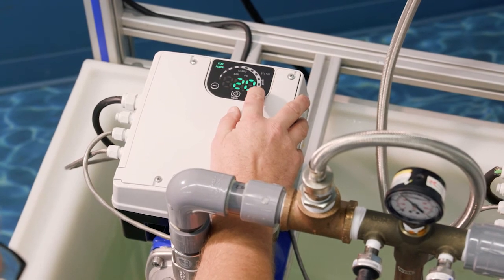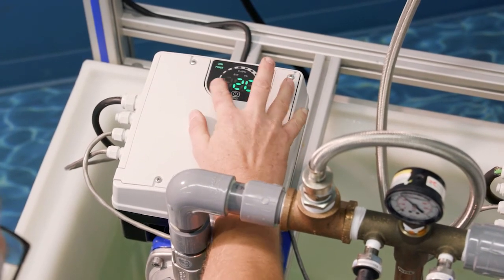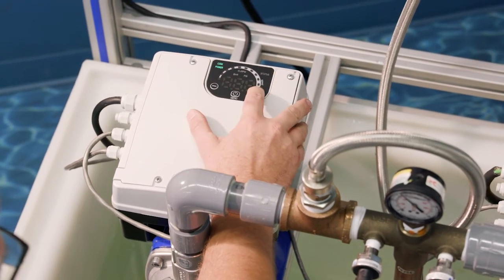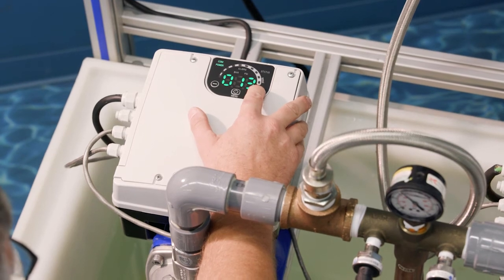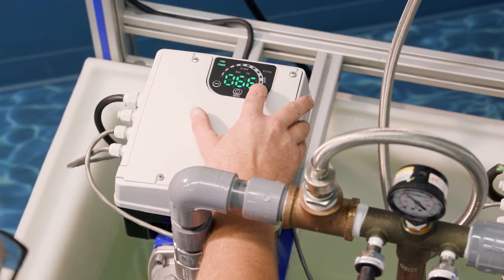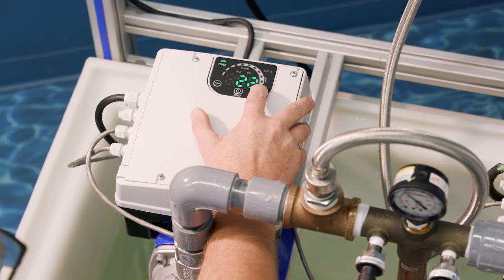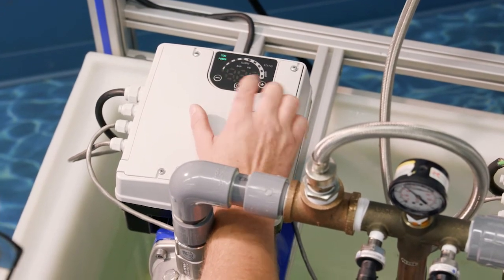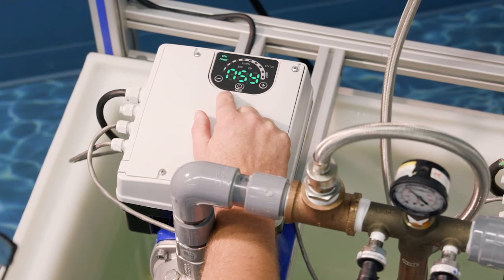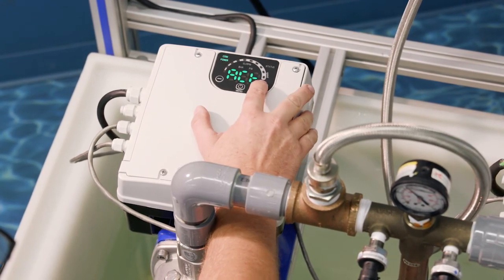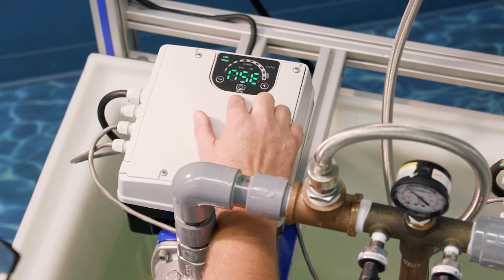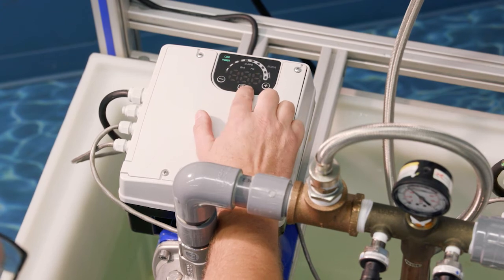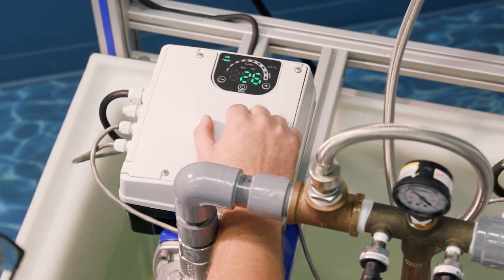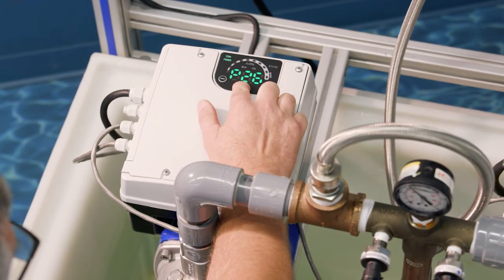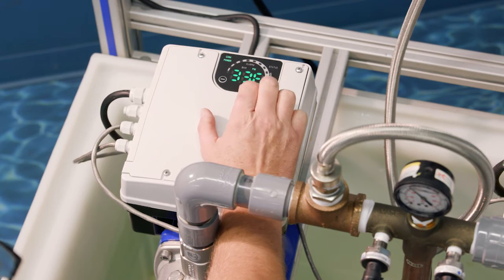So after a certain amount of time, we need to enter the password again. So just in case, let's do that again here. So let's go to 66. Allowing us to go to the additional parameters, and that's P25. So we can see that it was currently set at synchronous. Let's find serial cascade, and that's this one right here. So just hit the menu button again to save that, and we'll get out of that parameter menu by pressing and holding. It gets us back to the main menu.